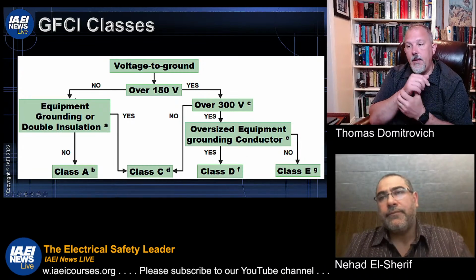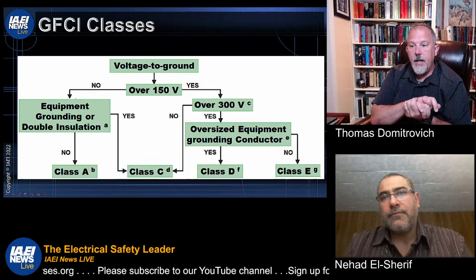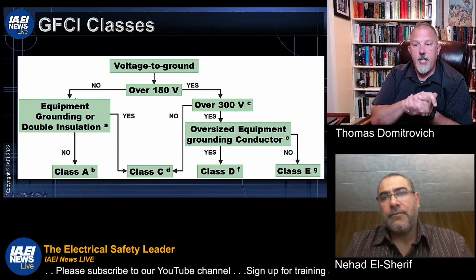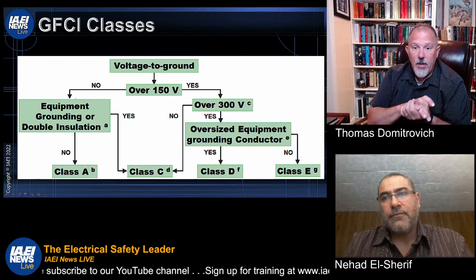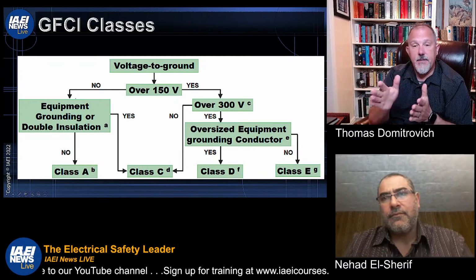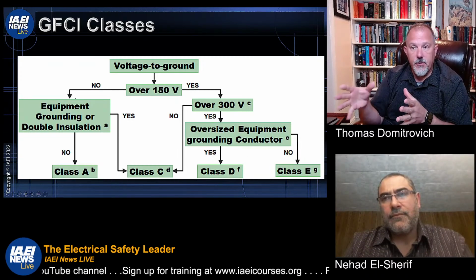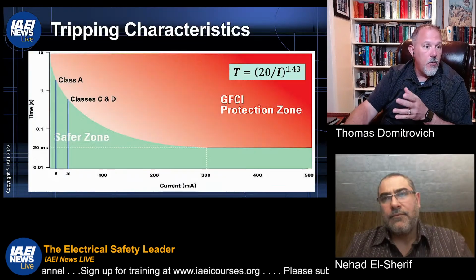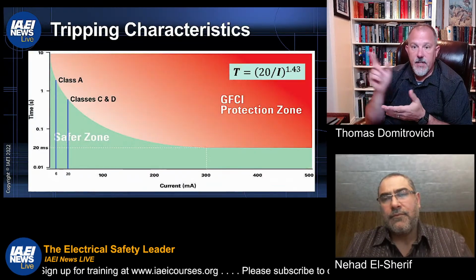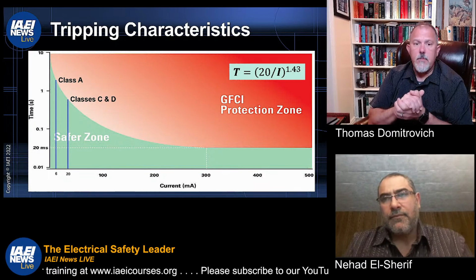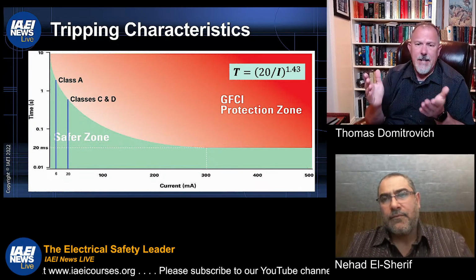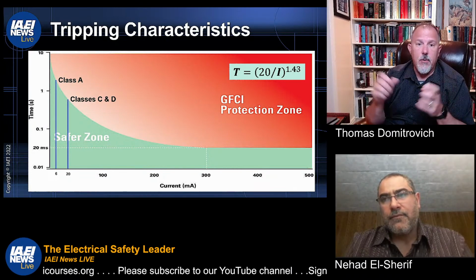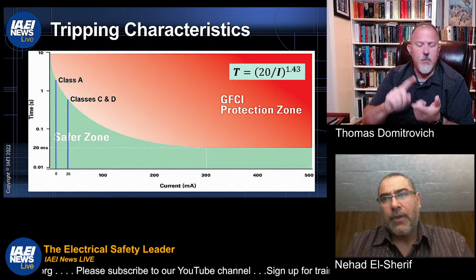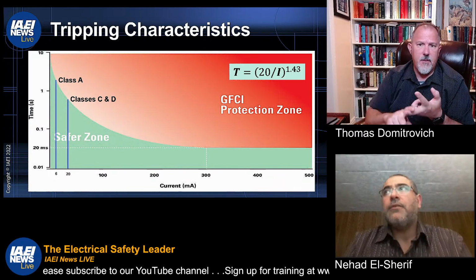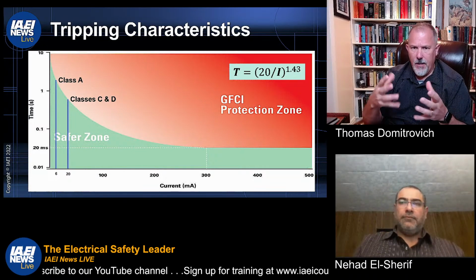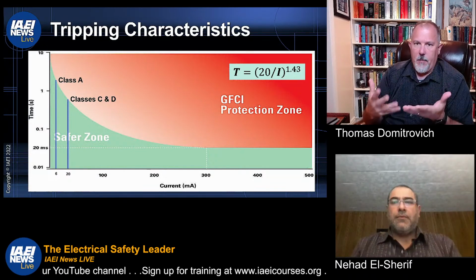So Fred B says, what difference is there in a Marina grade GFCI? So Fred, if you say GFCI, you're talking about a ground fault circuit interrupter. You're talking about a Class A device, which has that 4 to 6 milliamp trip time. And for a Marina grade, I don't know that there's any special category. You would probably want something that's weather resistant. It would have to be in a certain enclosure from an environmental perspective.